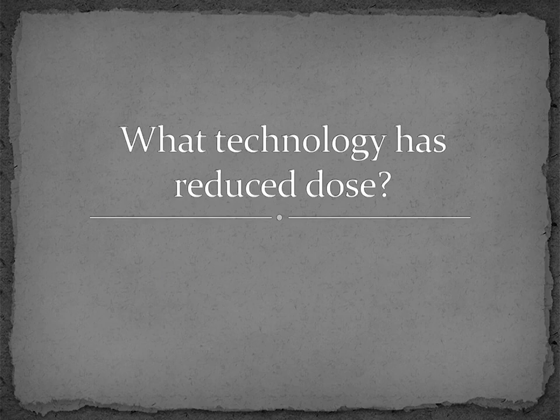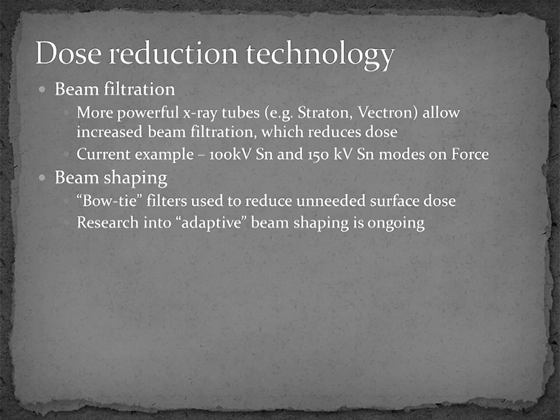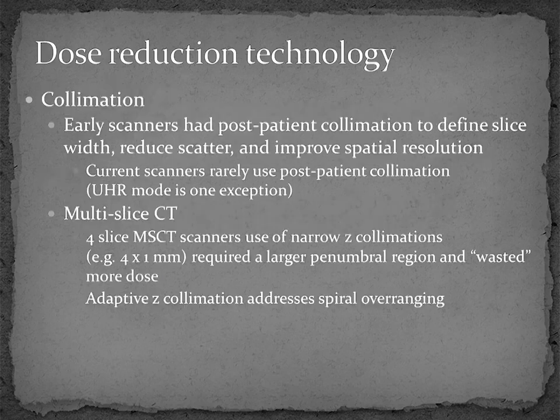So what are the technologies that have allowed this reduction in dose? Some of the techniques have to do with the system hardware, such as beam filtration and beam shaping, which remove photons that will not contribute significantly to the image formation but do contribute to the dose to the patient. Beam collimation, particularly for multi-slice CT scanners, continues to be an important part of the technology in order to preserve dose efficiency.